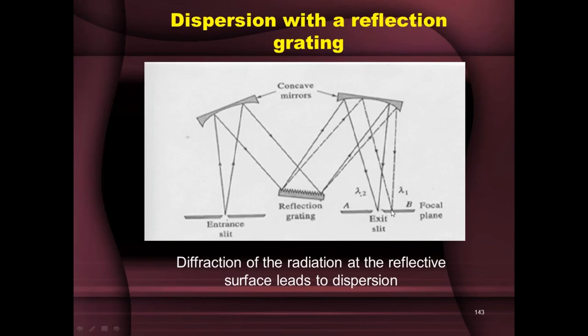If you want lambda 1 to fall on the sample, you rotate the grating. When the grating is rotated, lambda 2 shifts to one side of the focal plane and lambda 1 shifts right onto the exit slit. So, just as the prism was rotated, here the grating is rotated to get different wavelengths onto the exit slit. Diffraction of radiation at the reflected surface leads to dispersion in the case of gratings.